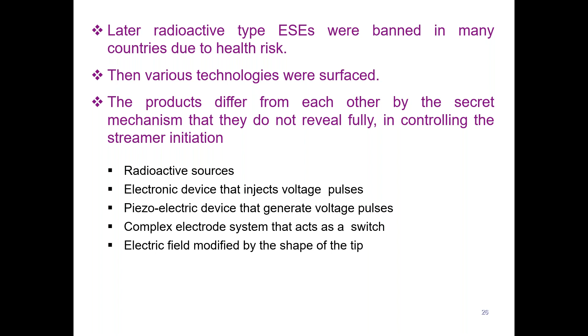The difference they introduced into the design of lightning protection technology is that since the ESE rod has a much higher physical height, they said if they can have one ESE rod usually put at the top of the building, they can replace all other air terminations. So what can be done with a very complex system of air terminations can be achieved, according to ESE manufacturers, by one air termination and one down conductor in most cases. They said that beyond about 20 meters there should be more than one conductor, but up to 20 meters they allow, even in present standards, one conductor under certain conditions.